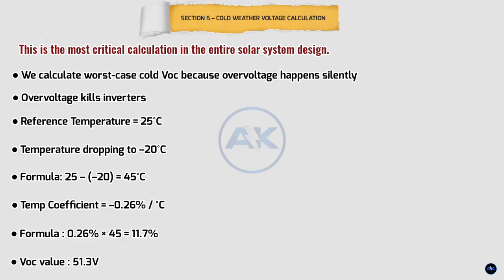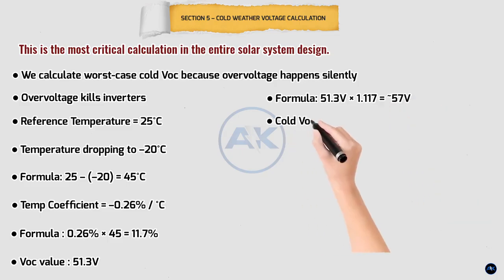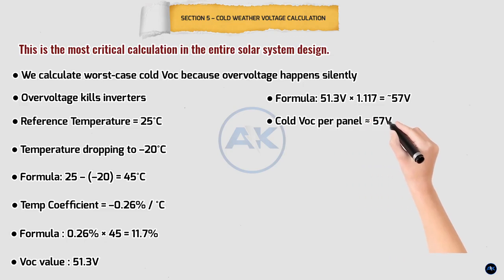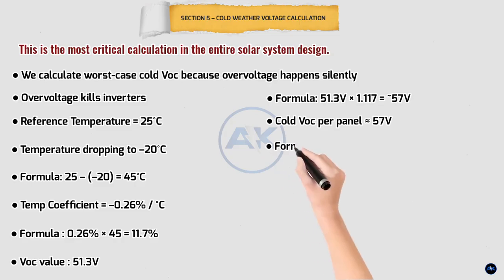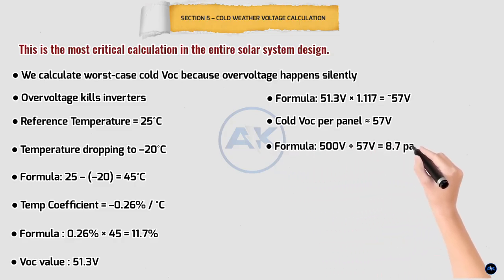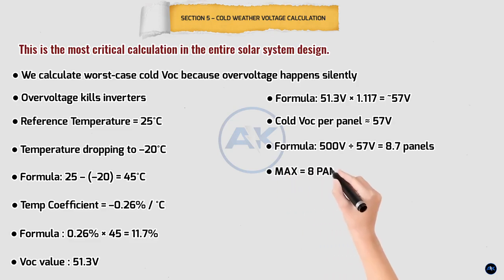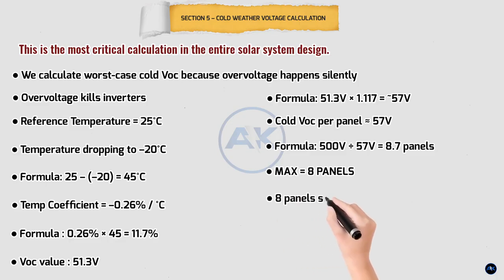Now we apply that increase to the panel's rated VOC. The rated VOC is 51.3 volts. 51.3 volts multiplied by 1.117 gives us a new cold weather VOC of about 57 volts per panel. Now we ask the most important question. How many panels can we connect in series without exceeding the inverter's 500-volt limit? 500 volts divided by 57 volts gives us 8.7 panels. Since we can't install a fraction of a panel, we must round down. That means the maximum safe number is 8 panels per string.